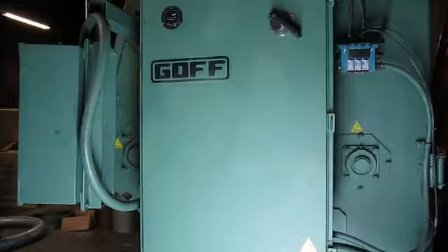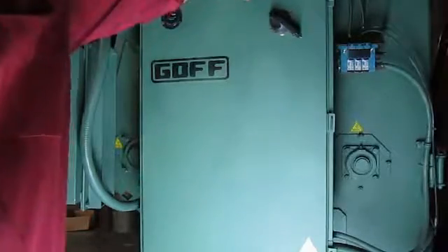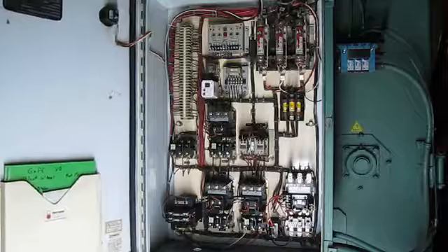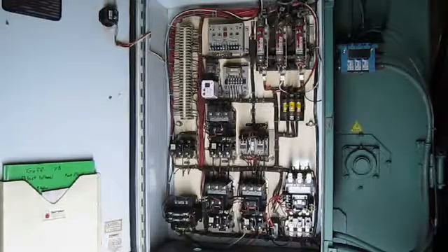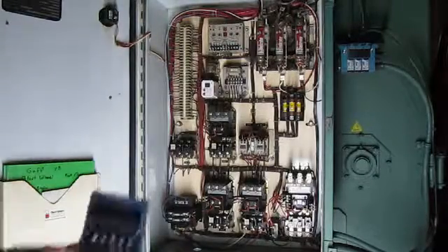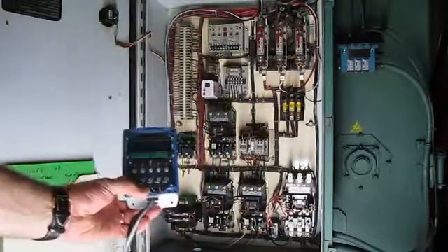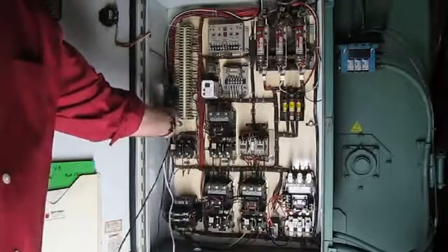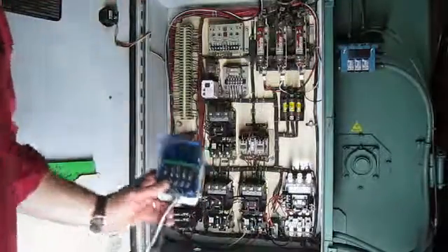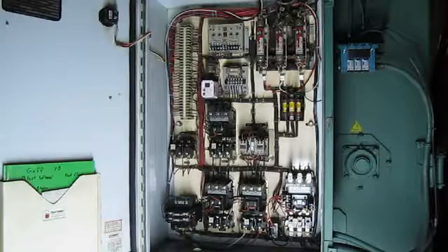So as we take a look at our machine here, I open up the control cabinet, and we can see this is an older machine made in the mid-90s. No intelligent controls, no microprocessors, no computers, anything like that, just motor starters. Things are pretty tight in there, not a whole lot of room, but we can still most definitely work with this small runtime recorder. You can see it can fit a couple of different places. You can put it on the ground, and it'll fit real nice in there.